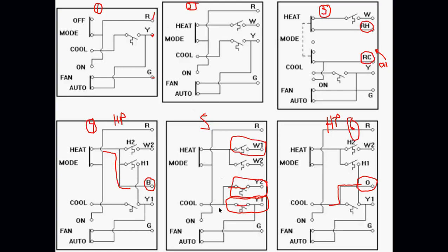Now, this is not part of every system that's out there. This is a very high-end system, okay? So specifically, the system has to be designed and manufactured to have this capability. But on higher-end homes, and this is very frequent in commercial environments, you will have a stage 1 and a stage 2 of both heating and cooling. In commercial environments, stage 1, a lot of times is we just bring in outside air. And stage 2. So what is that one called? What is that thermostat called? It's just a two-stage heat, two-stage cool. Again, the number 5 is two-stage heat, two-stage cool thermostat.